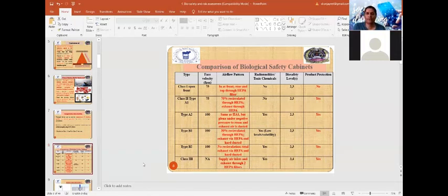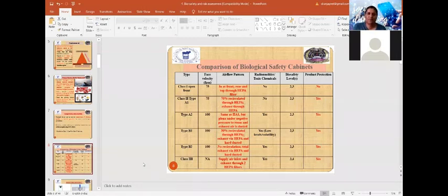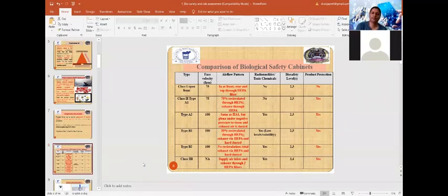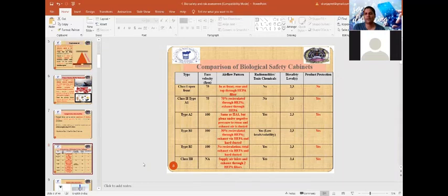Class 1 biosafety cabinets have an open front with a face velocity of 75 fpm. Airflow enters from the front and exhausts through the rear or top via HEPA filters. Class 1 cabinets can be used in BSL-2 or BSL-3 laboratories, but a major drawback is that there are significant chances of product contamination.